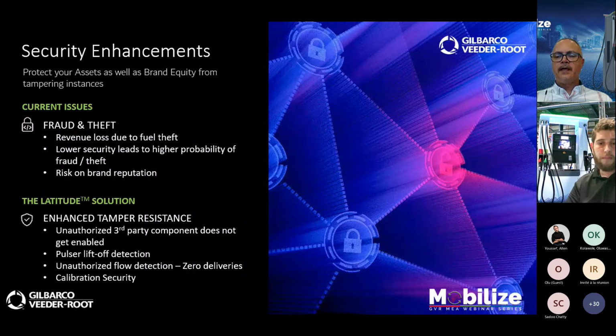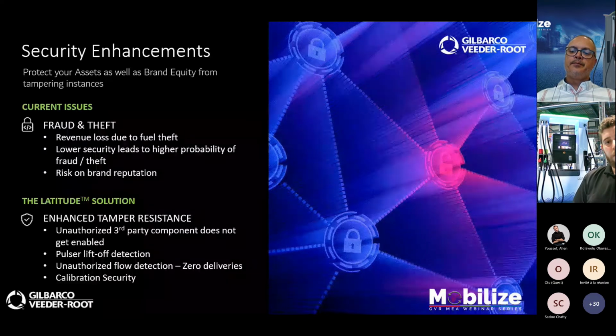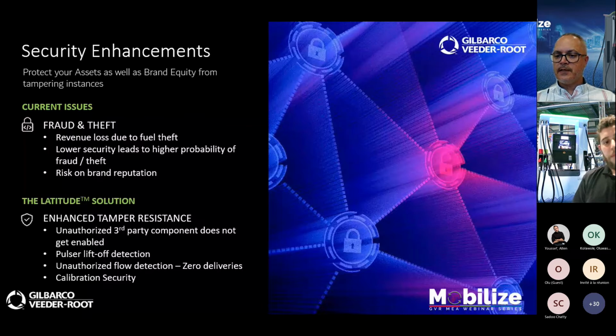The second thing is part of the calculator system, the pulser, which measures the amount of fuel going through the meter. It has lift detection, or lift protection. When the unit is lifted and its bolts undone, we get an error that locks the pump up and it will not dispense. That's a common way people try to defraud pumps.